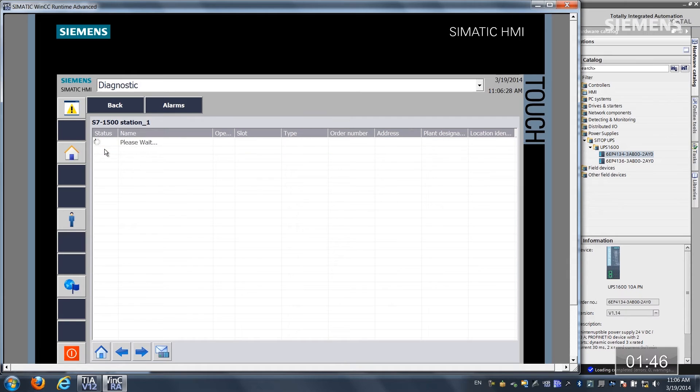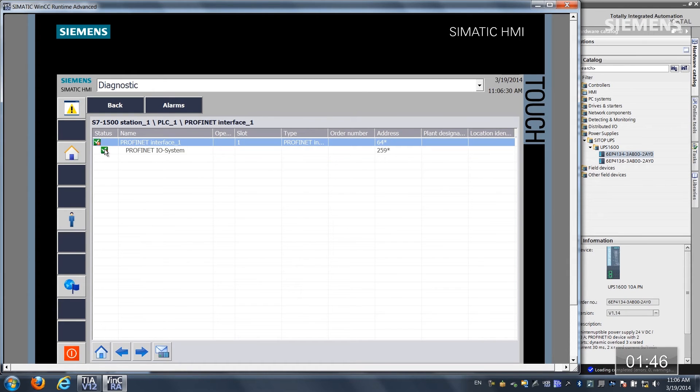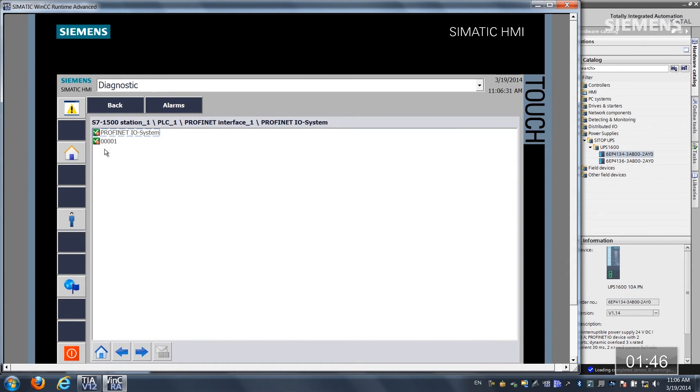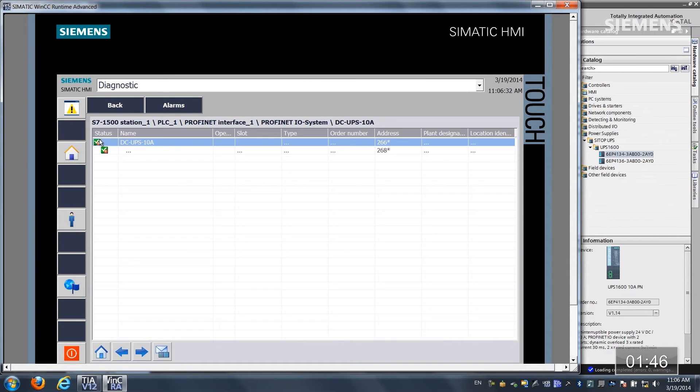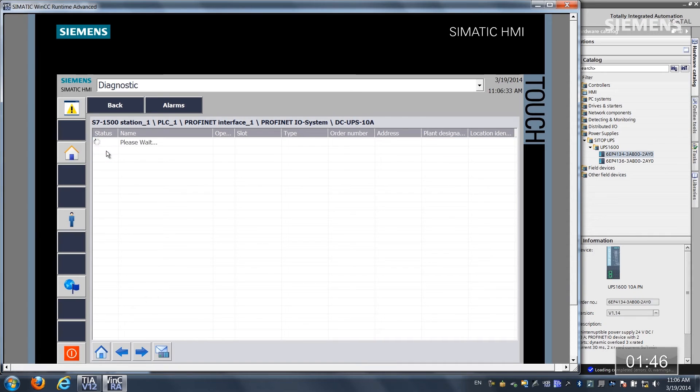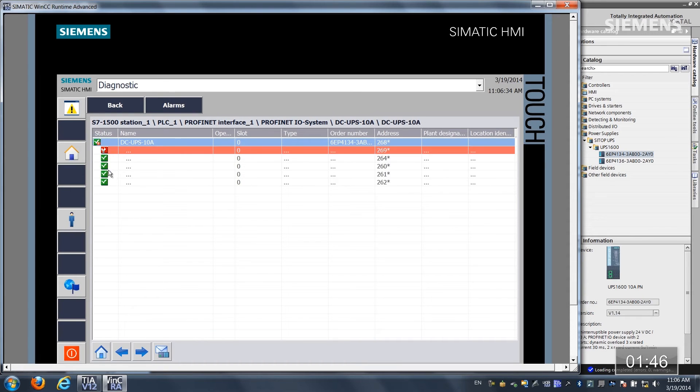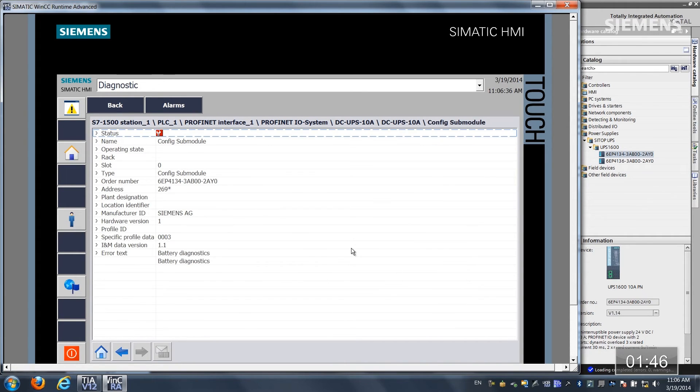Let's actually navigate down through all the way through the PROFINET system and there is the actual UPS and now you can see the breadcrumbs of where it is in the PROFINET architecture as well as its part number and it is a battery diagnostic.